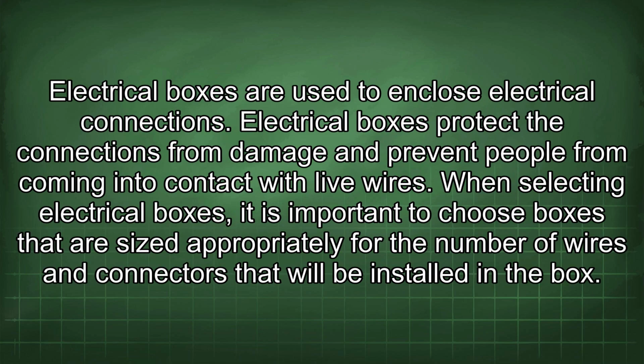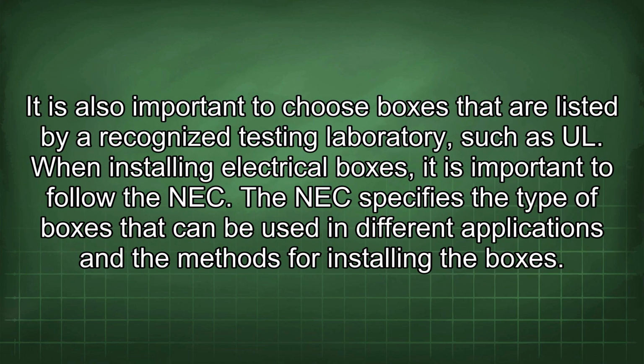Electrical boxes are used to enclose electrical connections. Electrical boxes protect the connections from damage and prevent people from coming into contact with live wires. When selecting electrical boxes, it is important to choose boxes that are sized appropriately for the number of wires and connectors that will be installed in the box. It is also important to choose boxes that are listed by a recognized testing laboratory such as UL. When installing electrical boxes, it is important to follow the NEC. The NEC specifies the type of boxes that can be used in different applications and the methods for installing the boxes.